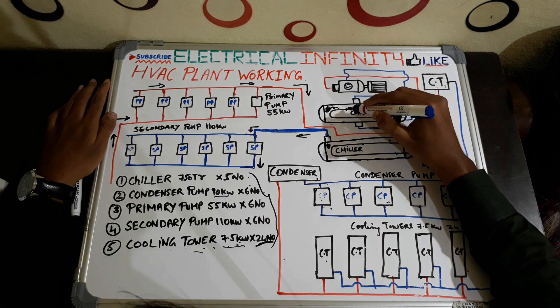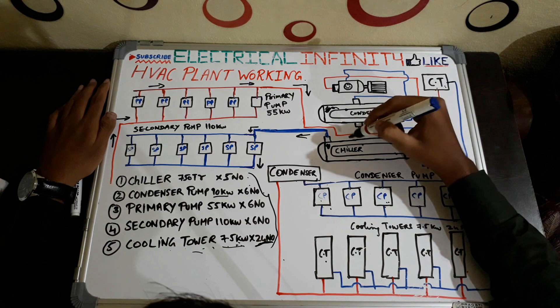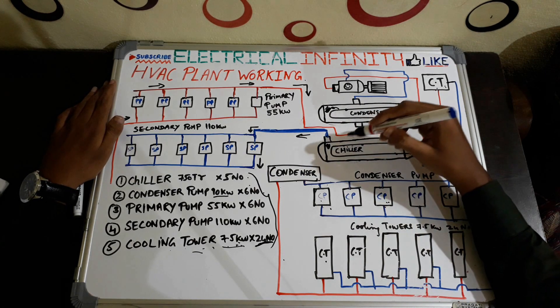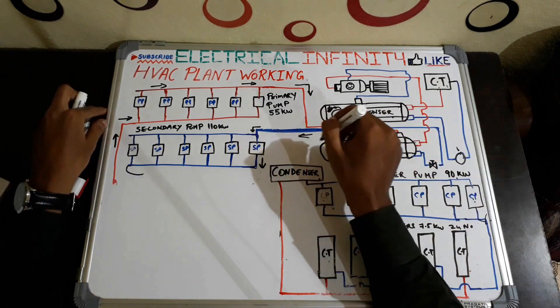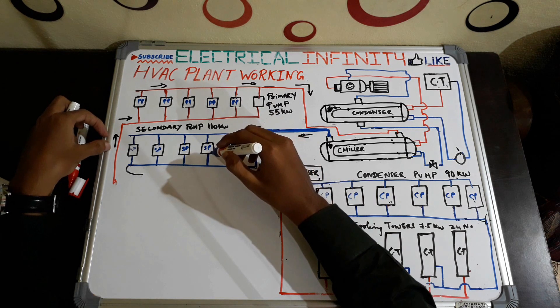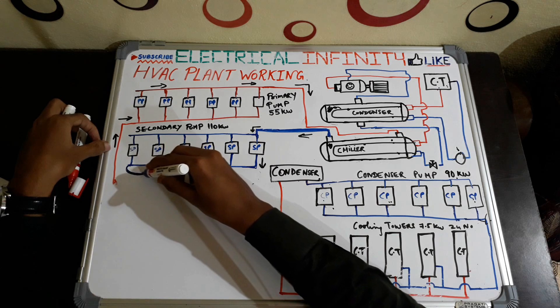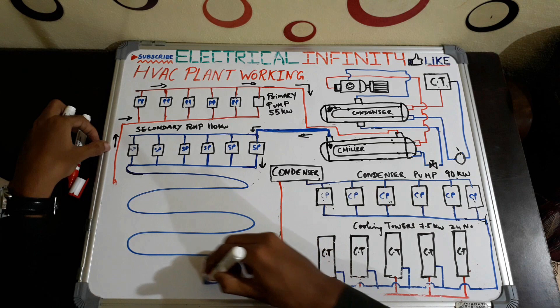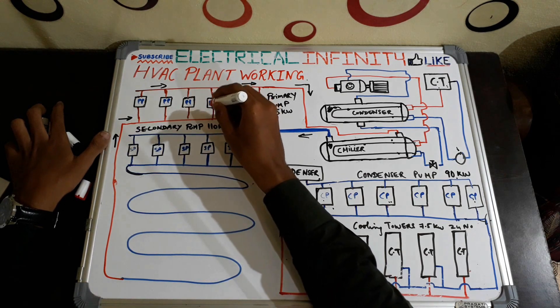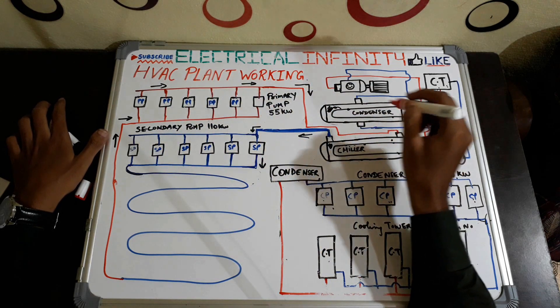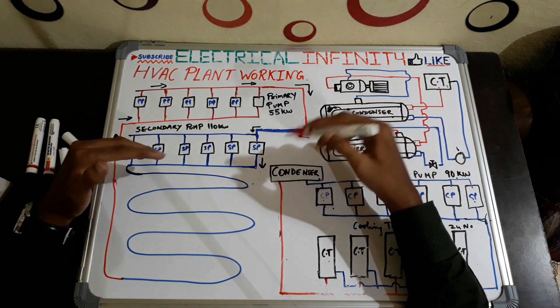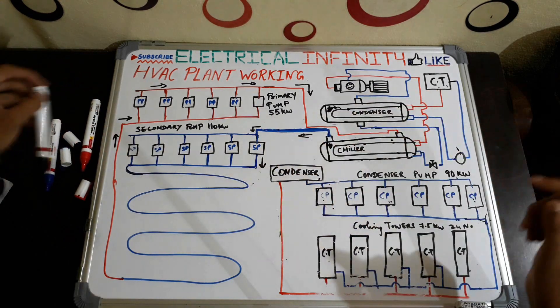In summary: in the condenser, heat exchange takes place between the refrigerant in the shell type and the cooling water in the tube type. In the chiller, the refrigerant is in the tube type and the building cooling water is in the shell type. The chilled water from the chiller is sent to the six secondary pumps of 110 kilowatt, which circulate it to the entire seven-floor building. After cooling the building's air, the water gets heated and is pumped back by the primary pump to the chiller for cooling — and this cycle repeats.